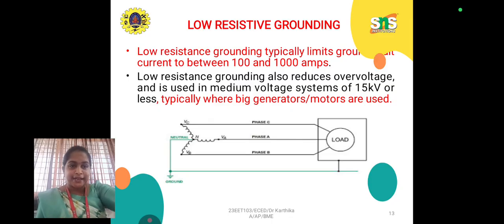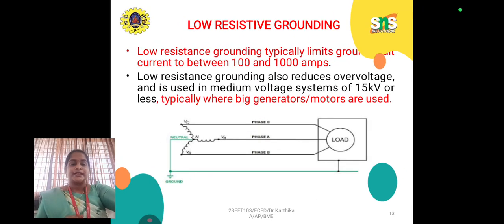See the diagram. Here we have load and we have ground neutral lines, and also we have three phase lines, phase A, B and C. It resists the flow of current in the range of 100 to 1000 amps. Typically, it is used where big generators and motors are used. Here, one more thing, this low resistance grounding also reduces over voltage, and it is used in medium voltage systems of 15 kilovolt or less.